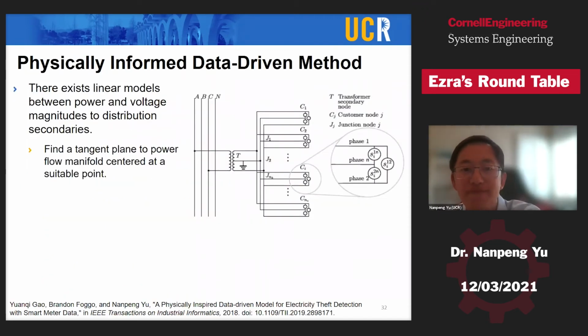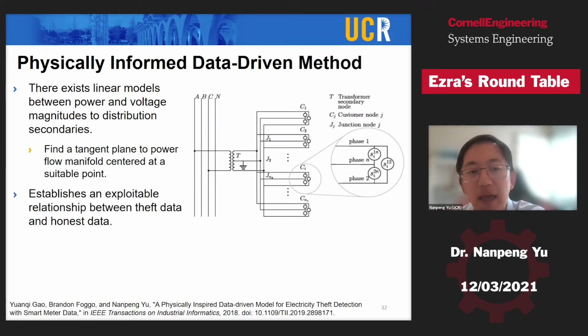So we developed this physics-informed data-driven algorithm. We found that there actually exist some linear models between the power and voltage magnitude for each of the distribution secondaries. All we need to do is find a tangent plane to this power flow manifold centered at a suitable operation point.